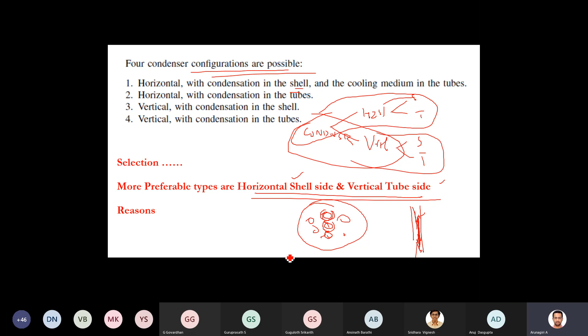In the case of vertical tube side, condensate will form and flow due to gravity. It's like a forced convection, it will move very fast, so vertical tube side will give more heat transfer coefficient. In the other case, horizontal tube side, the condensate forms over the surface and looks like laminar flow, so it won't give a better heat transfer coefficient. Initially it will be saturated vapor, then when it leaves the tube, it may be saturated liquid or a mixture of liquid and vapor. Here it would be vapor, then condensate will form, so you can observe different flow regimes when it flows horizontally.